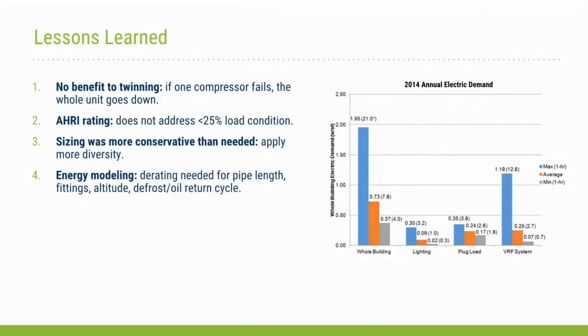As has been mentioned, for energy modeling, there are not very many tools that can natively model these systems. And Derating does need to be taken into account for actual installed pipe length, the fittings, the altitude of the installation, and also defrost oil return cycles that can temporarily interrupt performance. The graph that you see on the right is actual annual electric demand for the building.